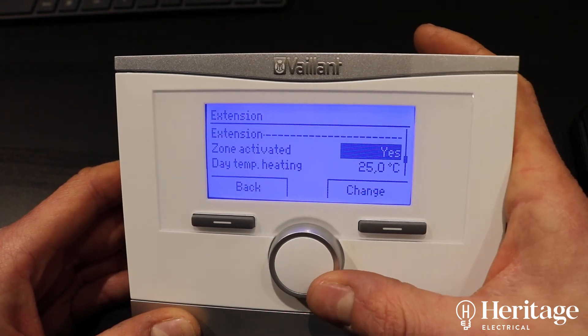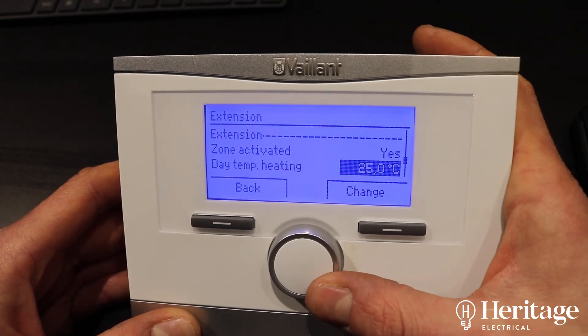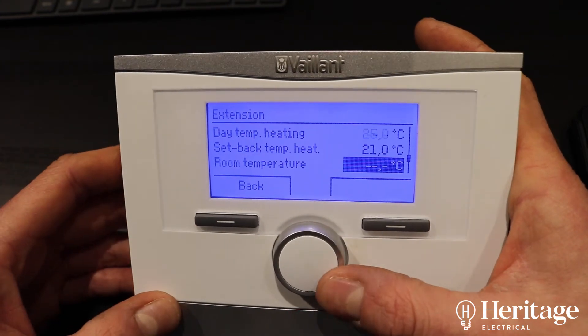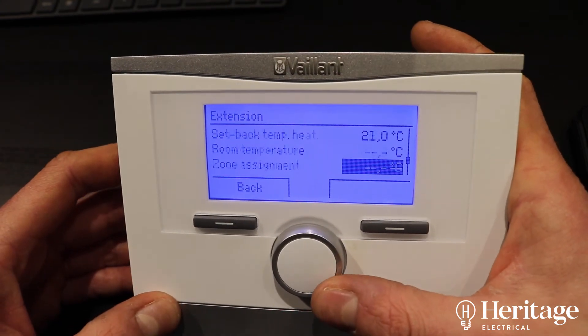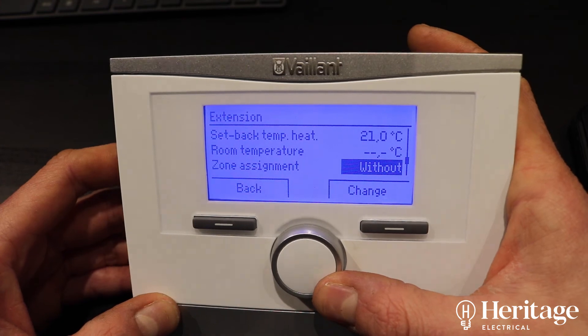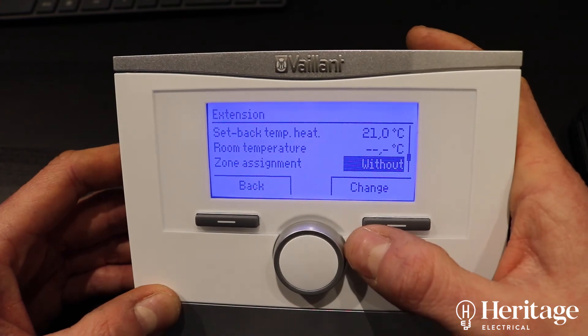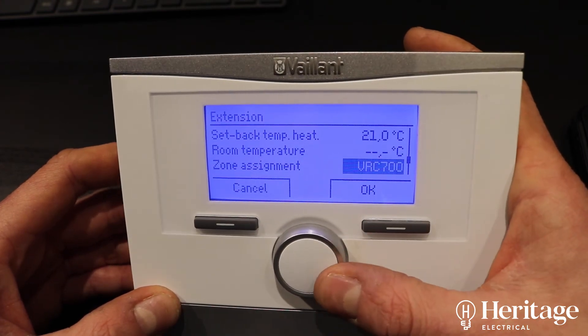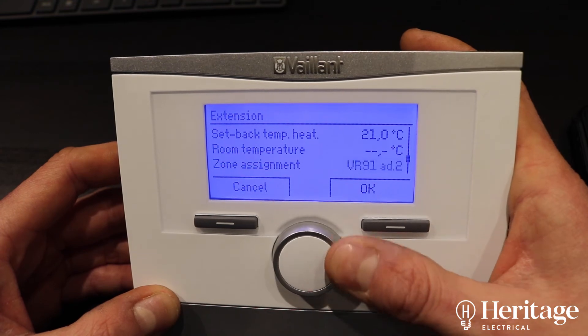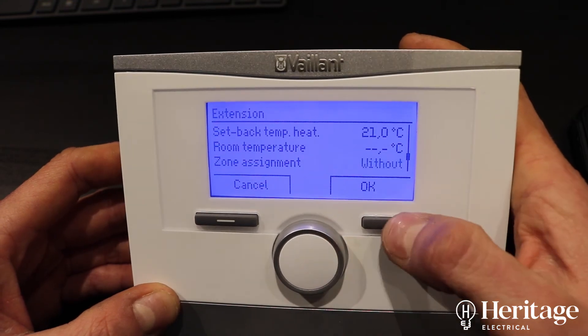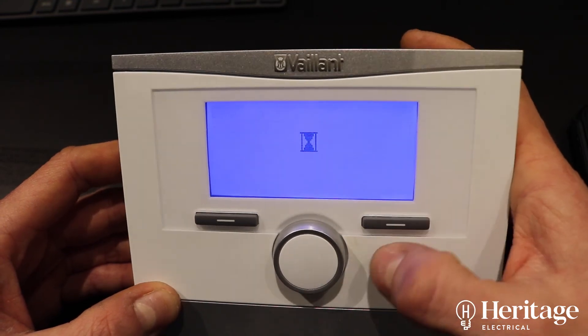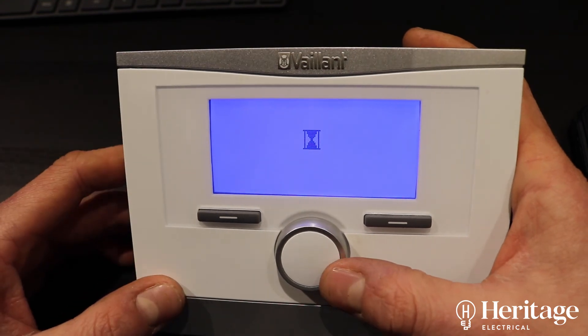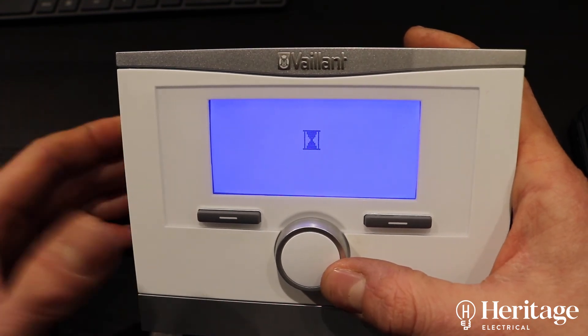Zone two covers all the underfloor heating in the extension, which we're using the heat miser system to control. You can see here zone assignment is set to 'without', so we've not got any of the VRC controllers asking for heat — we are using the heat miser room stats and the UH8 wiring centre to do the calling for heat.